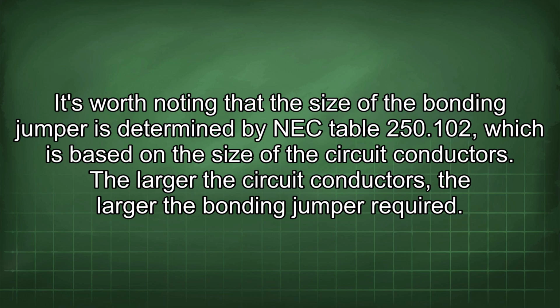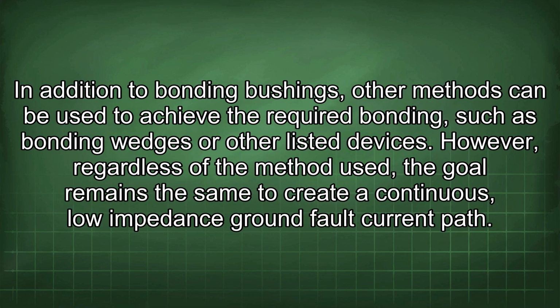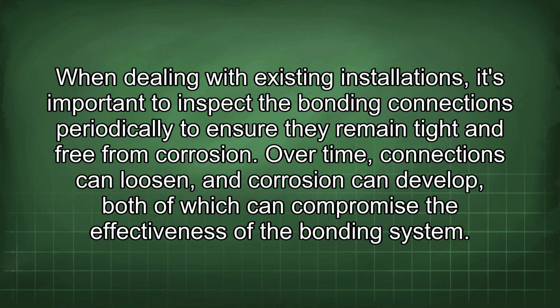It's worth noting that the size of the bonding jumper is determined by NEC Table 250.102, which is based on the size of the circuit conductors. The larger the circuit conductors, the larger the bonding jumper required. In addition to bonding bushings, other methods can be used to achieve the required bonding, such as bonding wedges or other listed devices. However, regardless of the method used, the goal remains the same: to create a continuous, low-impedance ground fault current path. When dealing with existing installations, it's important to inspect the bonding connections periodically to ensure they remain tight and free from corrosion.